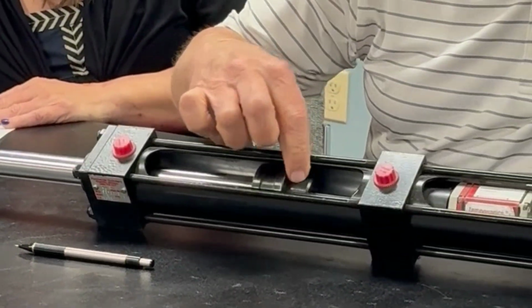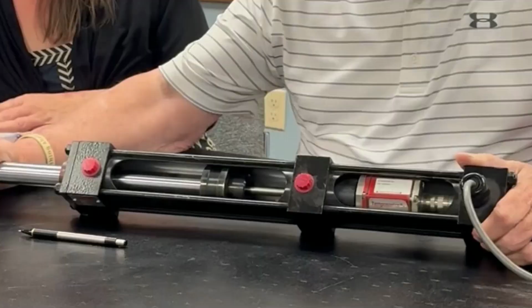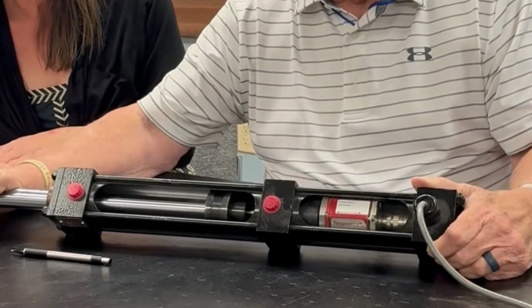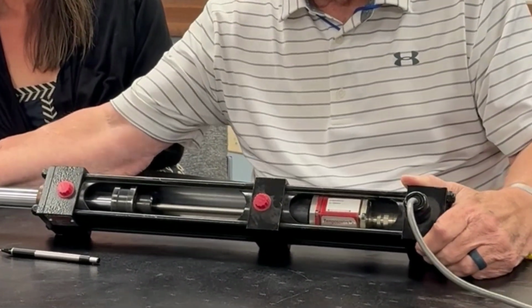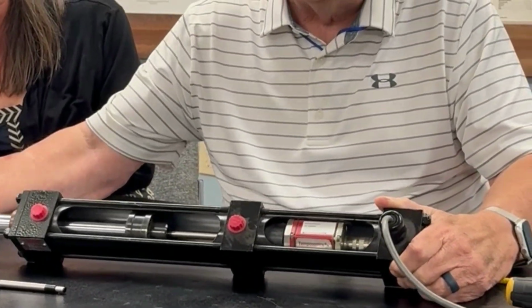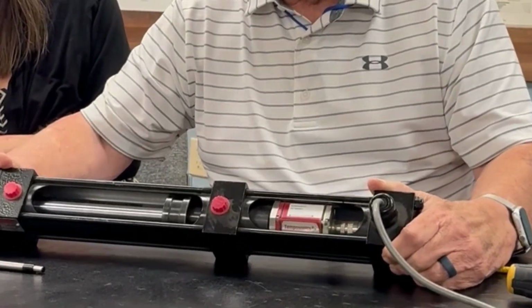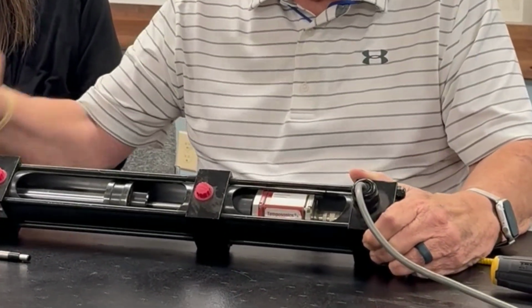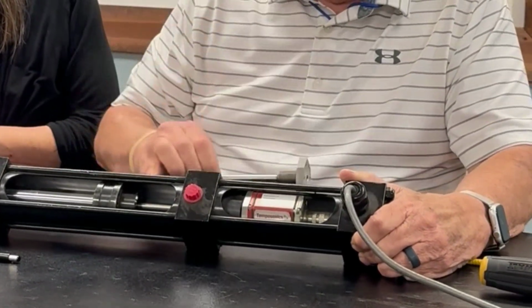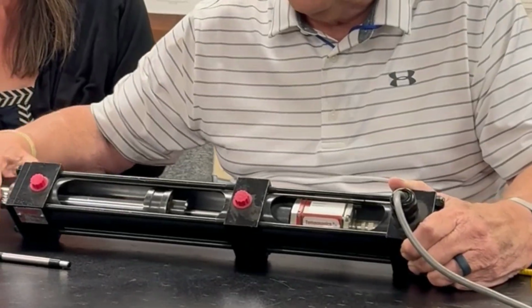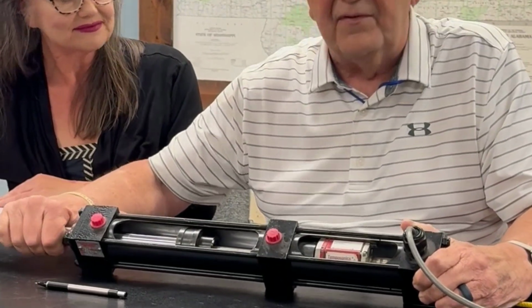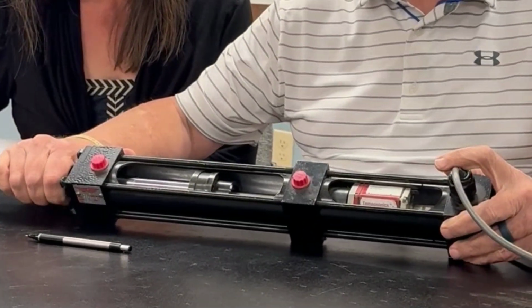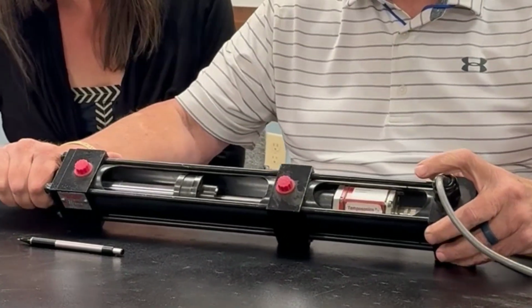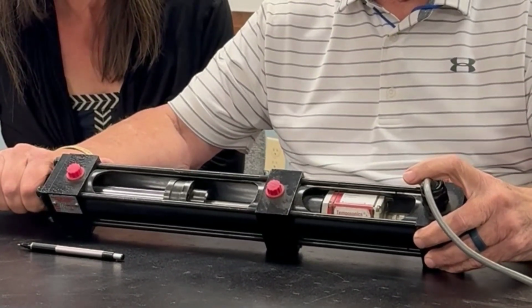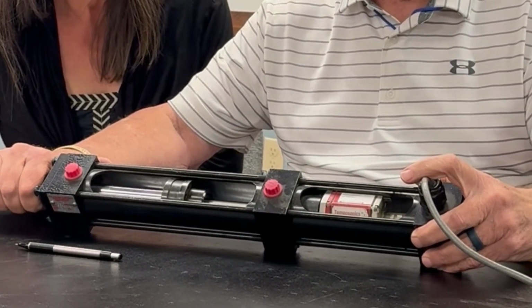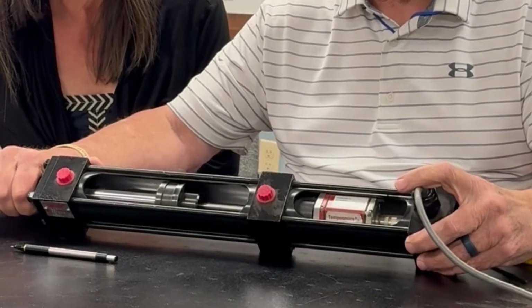Inside the piston of the cylinder is a magnet. So when the cylinder moves in and out, you can see how it goes up and down the rod of the transducer. It interacts with the waveguide inside this rod, which bounces the signal off the electronics down to the magnet and measures the time it takes for the signal to get back. Therefore, it's a completely non-contact sensor.